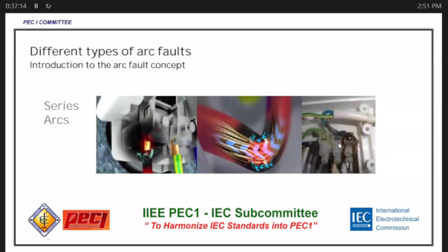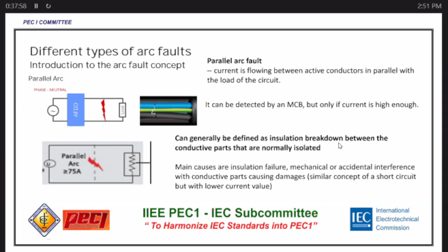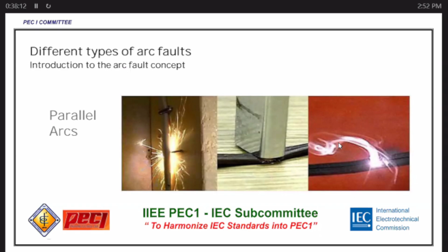So, how about the parallel arc? This is the parallel arc. If you look at it, the main causes are insulation failure, mechanical or accidental interference with conductive parts that causes damage. So, similar concept to a short circuit. This is what we call the parallel arc fault. This parallel arc fault can be detected by your miniature circuit breaker, but only if the current is high enough. If the current is not high enough, there would be no detection. That's why we sometimes get fires. These are the classical examples of the parallel arc fault concept, as shown in the illustration.